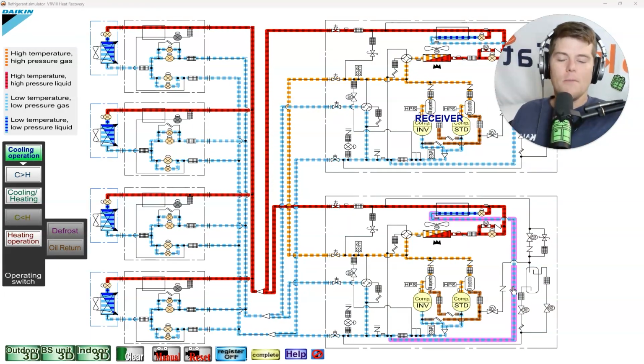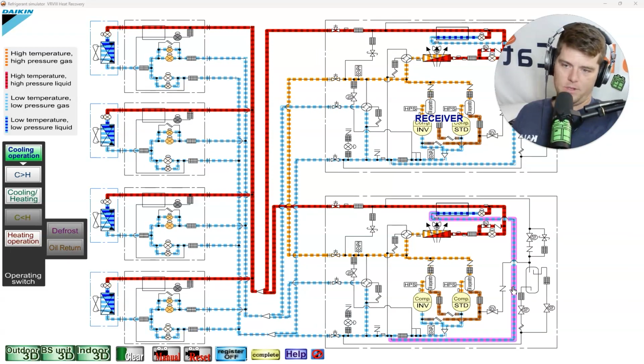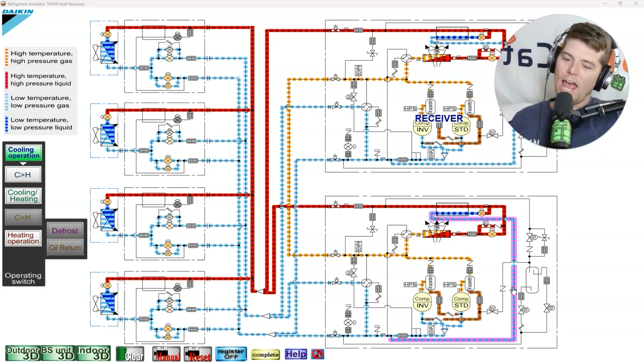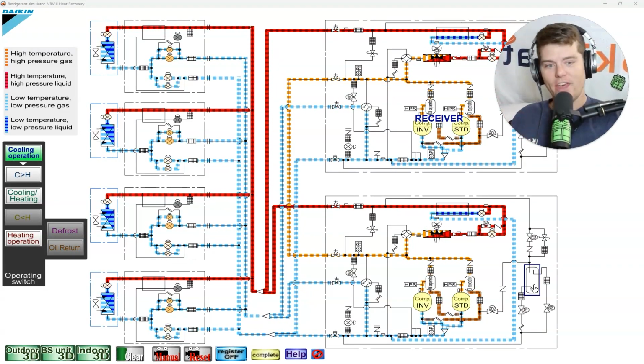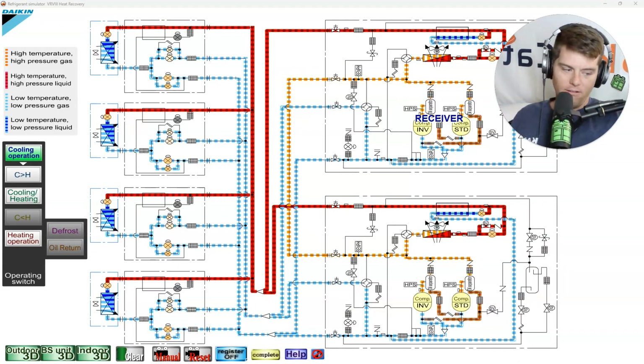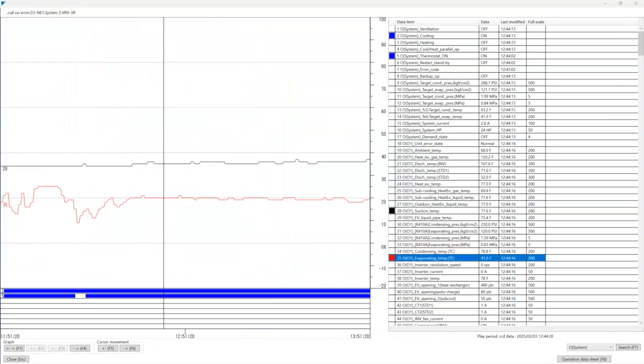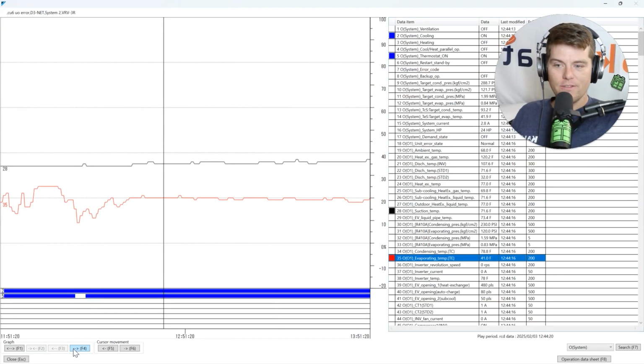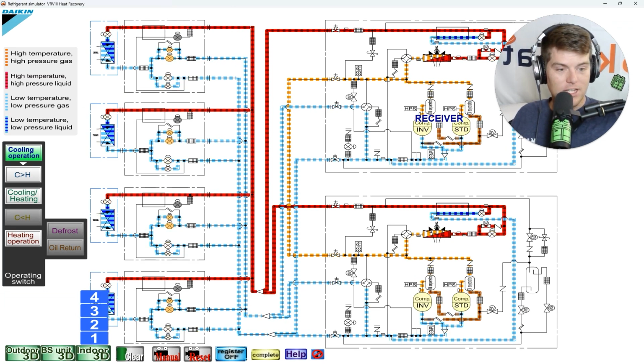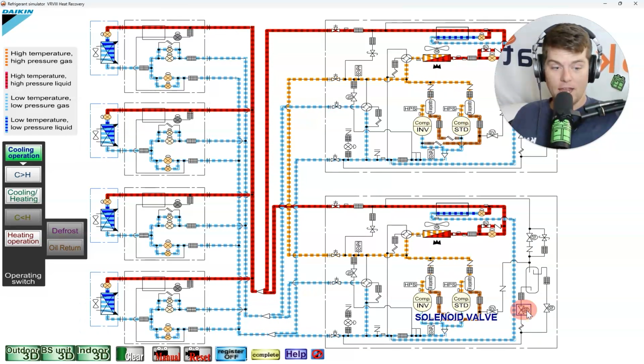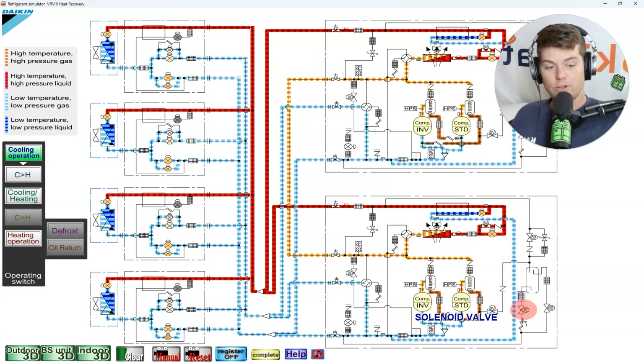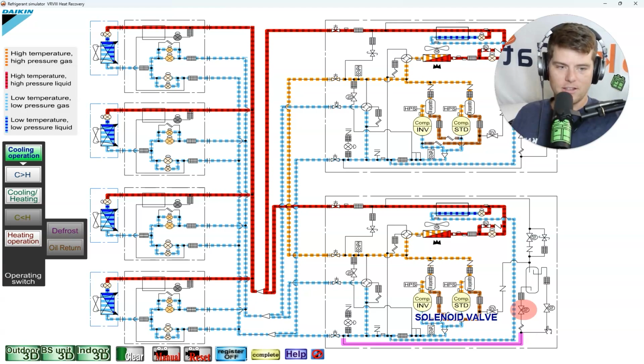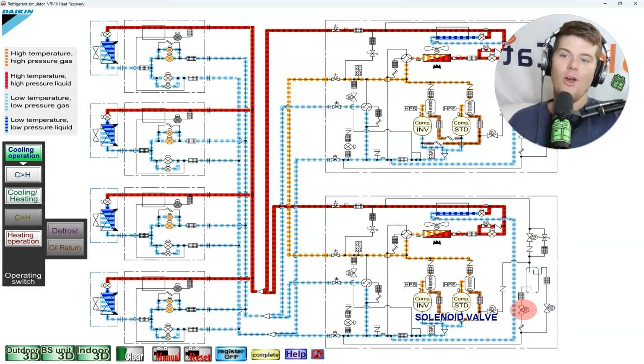Now, why does that matter? Because if the demand is low on the system, it's going to pull gas from the system. Okay, easy concept. Great, got it. What happens when the system is undercharged and it goes to add that refrigerant back to the system? Well, I'm so happy that you asked. It looks like this. When your liquid receiver is full of liquid and I put a full demand on the system, what happens? It starts to empty the receiver. How does it empty the receiver? It opens up this bottom line here, right, and allows liquid refrigerant to trickle through a capillary tube back into the suction line, and it charges the system over time.